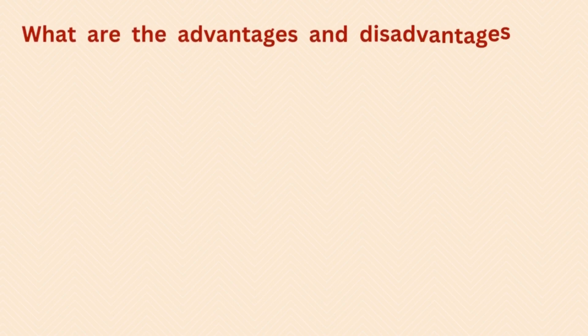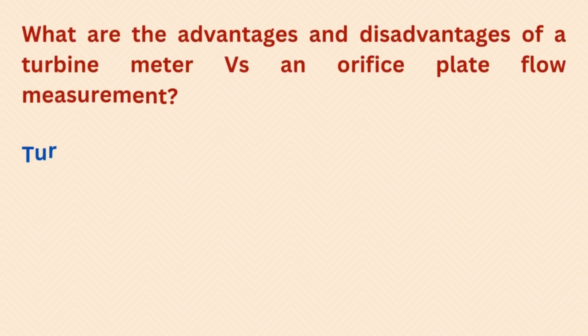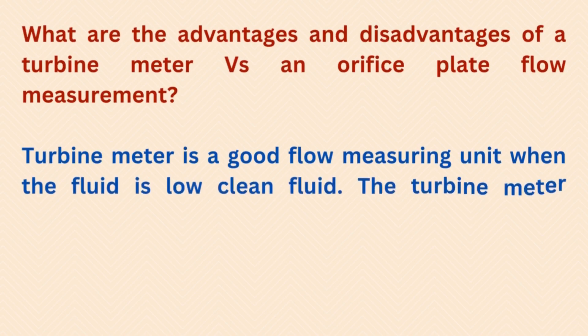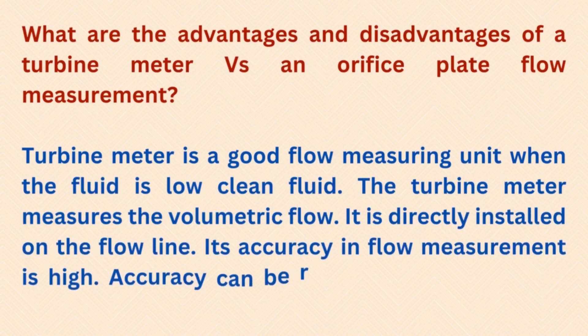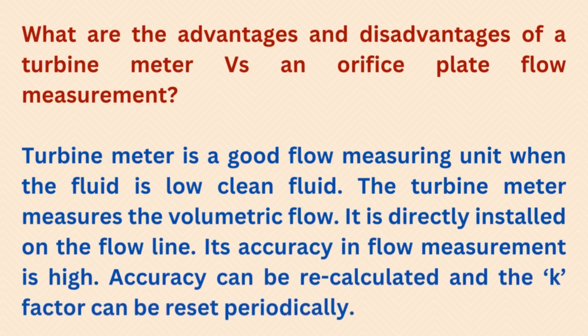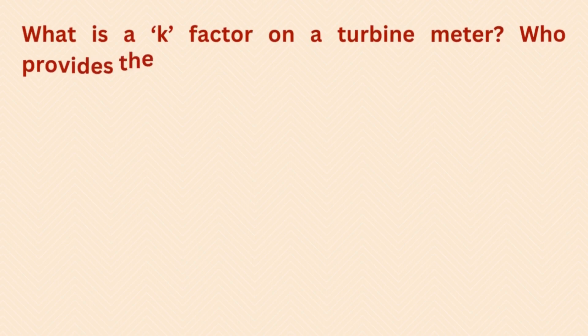What are the advantages and disadvantages of a turbine meter versus an orifice plate flow measurement? A turbine meter is a good flow measuring unit when the fluid is a clean fluid. The turbine meter measures volumetric flow; it is directly installed on the flow line. Its accuracy in flow measurement is high, and accuracy can be recalculated and the K factor can be reset periodically.